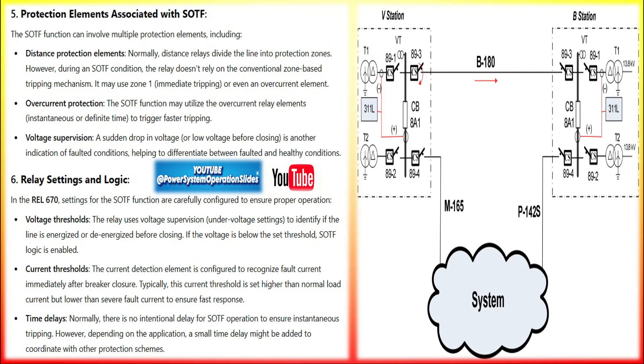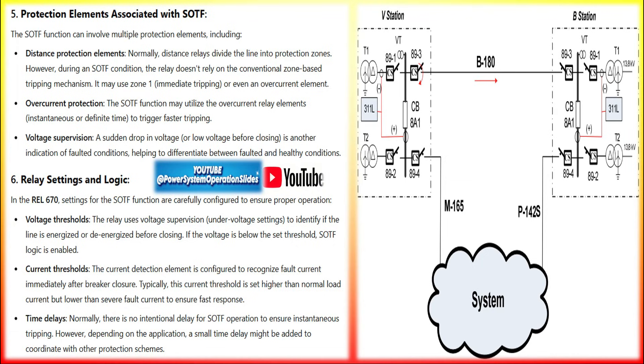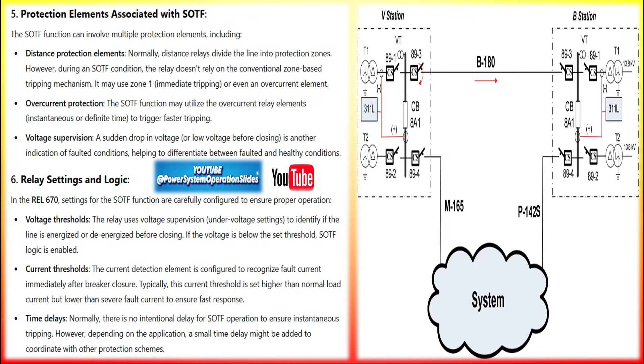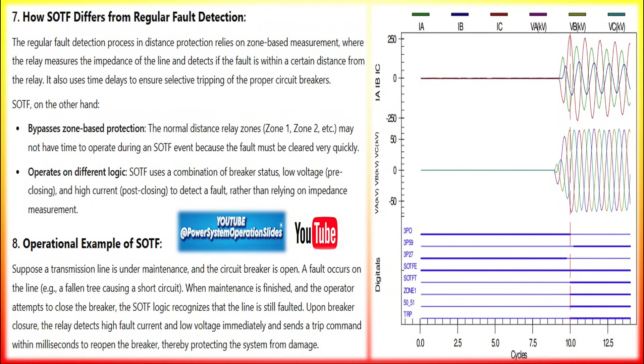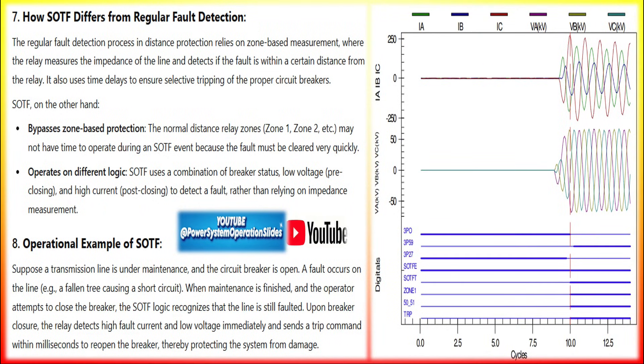Typically, overcurrent and distance protection elements have some inherent delay to ensure stability during normal operating conditions. SOTF, however, bypasses these delays to act immediately, preventing equipment damage and protecting breakers, transformers, and the line itself from damage caused by prolonged fault current exposure.